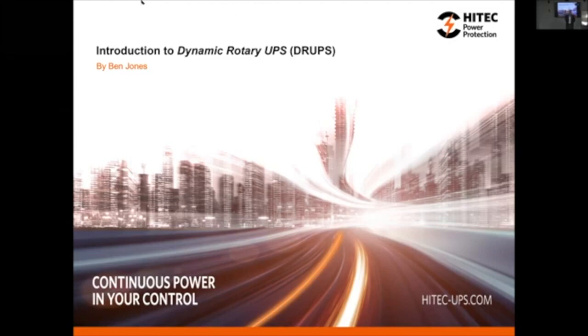Today, we're going to talk about diesel rotary UPS systems. These systems are very popular in Europe and are starting to get more traction here in the US. I've always been intrigued by the diesel rotary UPS. It has a lot of advantages. First of all, you can put it outside, it doesn't have to go in the building. It also can be delivered at medium voltage or higher voltage, 4160 volts or even higher, which prevents you from banging your head against 480 volts, 4,000 amps.